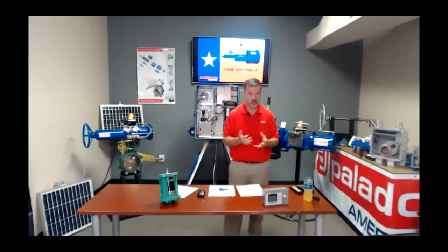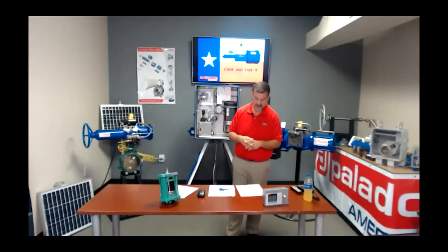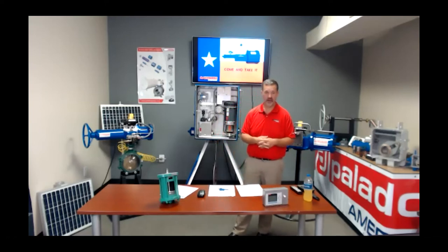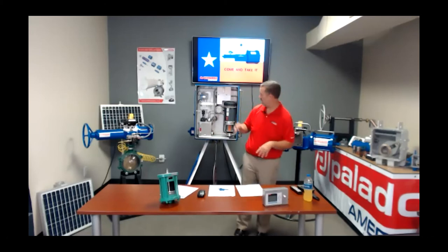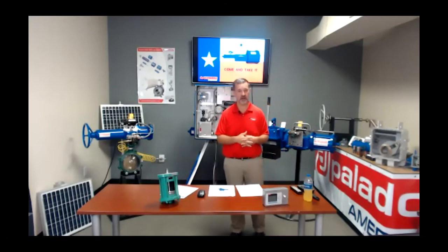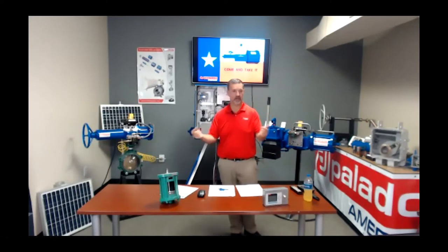We offer battery backup so that if a customer has utility power and loses it, the system continues functioning. The control system is available in both analog control — such as 120-volt AC or 24-volt DC to open and close — and digital control. For example, this unit has Modbus built in right from the factory. It can act as a host or as a slave, so if you have multiple units at a location, the first unit can act essentially as a router and all the others wire back to it, cutting down individual wiring to each unit.